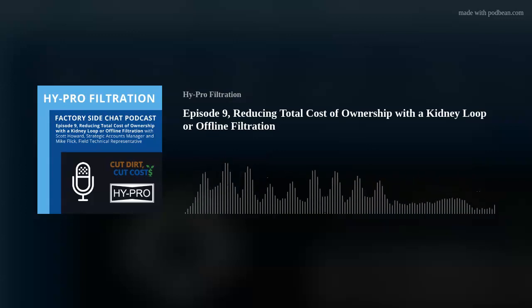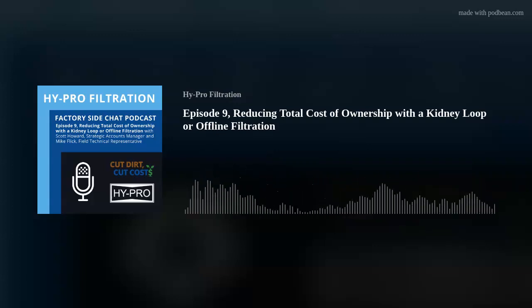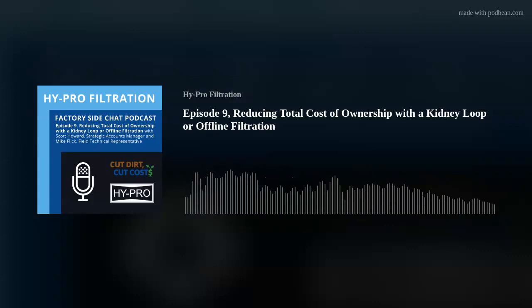And the same thing on your return filter. Anything that happened out during the work, now that oil is coming back, your return filter is just catching that debris from coming into the tank. So because your main pressure and return filters are now just acting as protectors or guardians, and your kidney loop is really setting the cleanliness level of your system, everything seems to last longer.